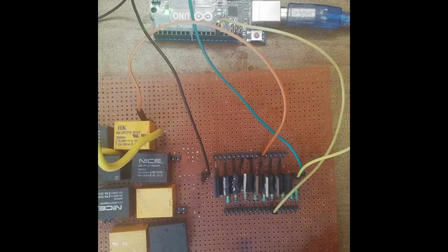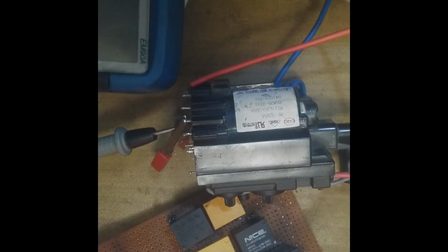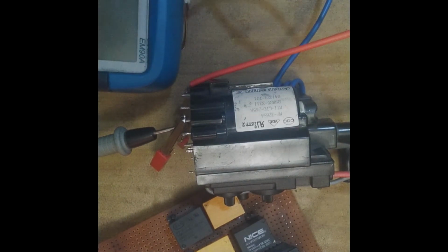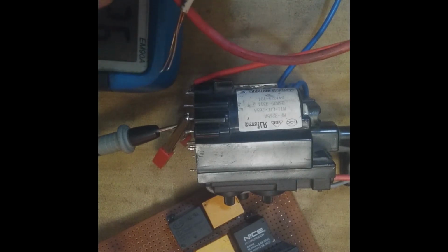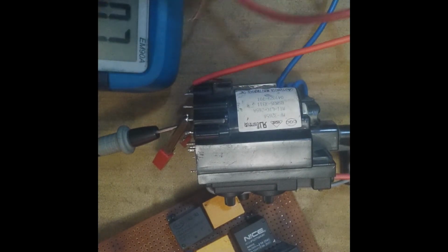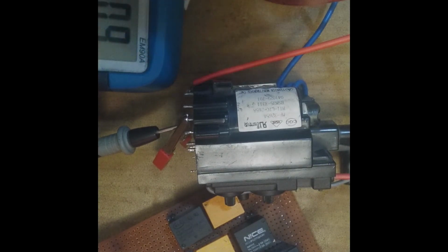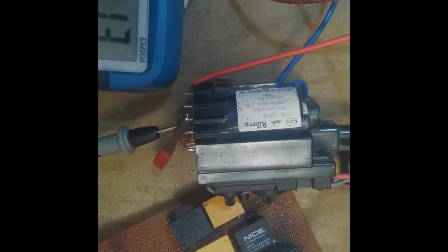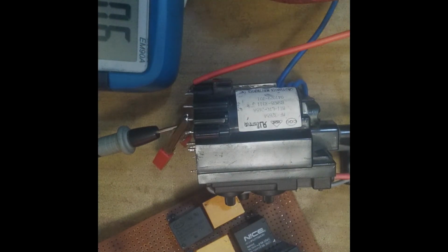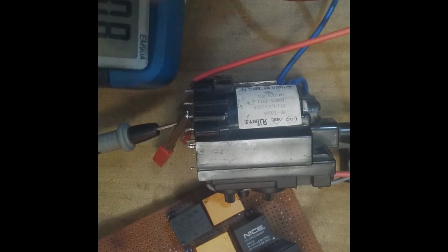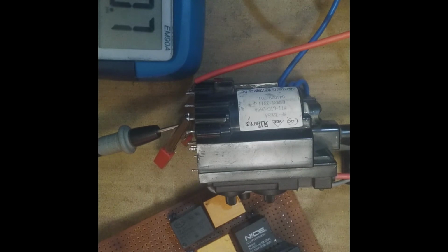Now we are going to do the polarity test on the transformer. To do the polarity test, connect the positive lead of your voltmeter to the wire coming out from the suction cup. Connect the negative lead of your voltmeter to the high voltage secondary terminal's neutral or negative point. Take the ground of the 12-volt power supply and connect it to the point A, and take the positive terminal of the 12-volt power supply and connect it to the wire that goes into the common of the tripping relay.